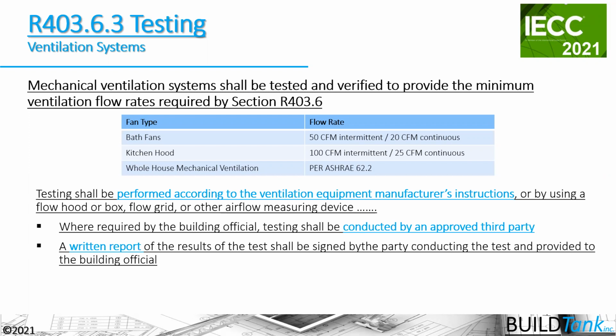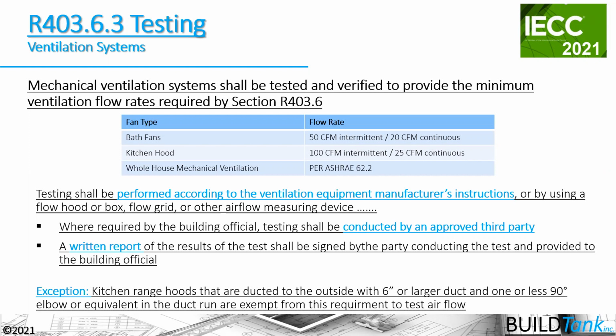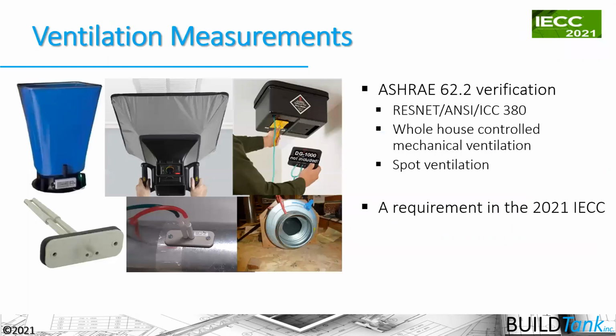So it continues, this requirement continues, it says that we have to test according to manufacturer instructions, and it has to be conducted by a third party, and we have to provide a report to the code official that these things have tested and passed as well. There is an exception for kitchen hoods because kitchen hoods are very difficult to test. So if you have a 6-inch run from your kitchen hood all the way to the outdoors and there's no more than one 90-degree elbow in that duct, you don't need to test it. There's going to be an assumption that it's able to push 100 CFM of air.